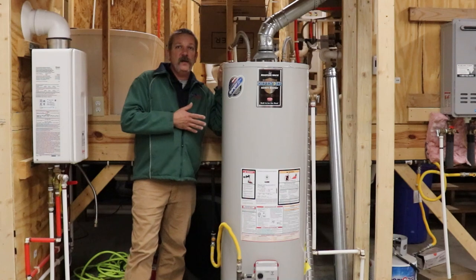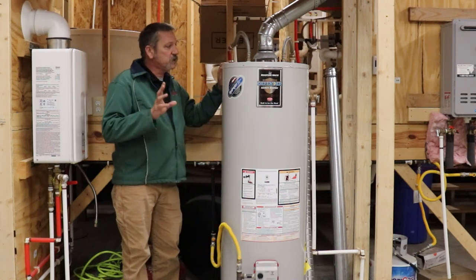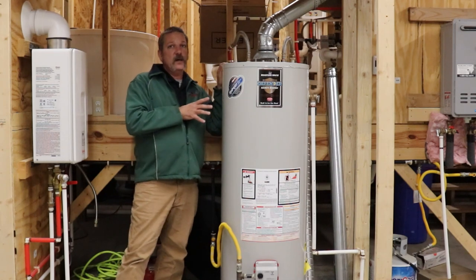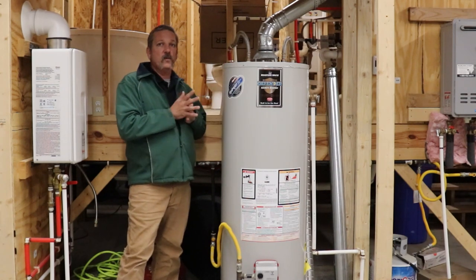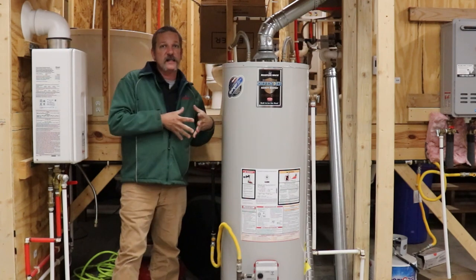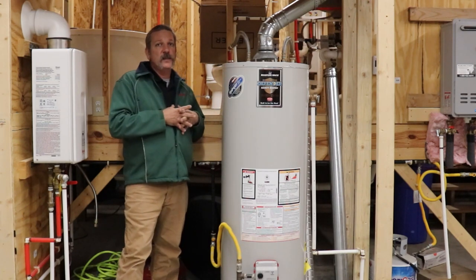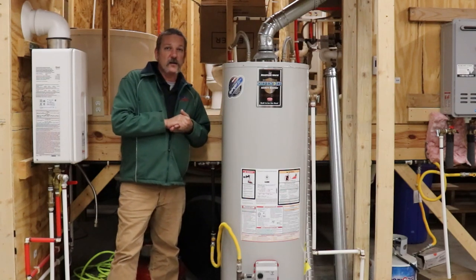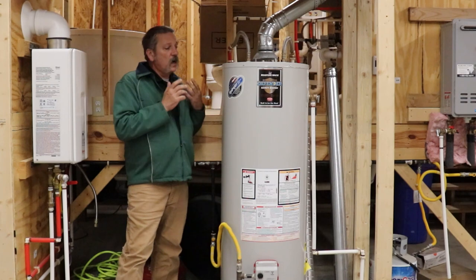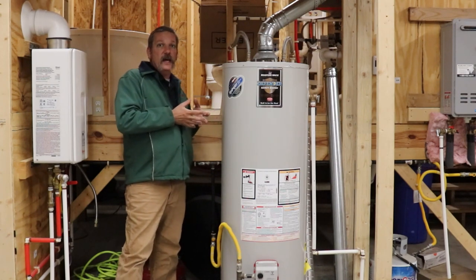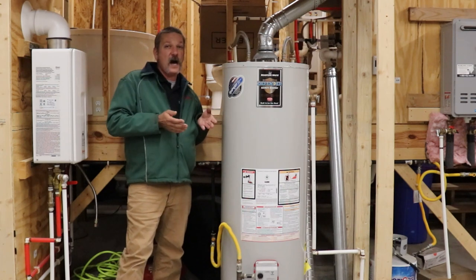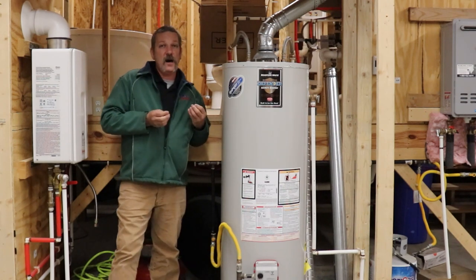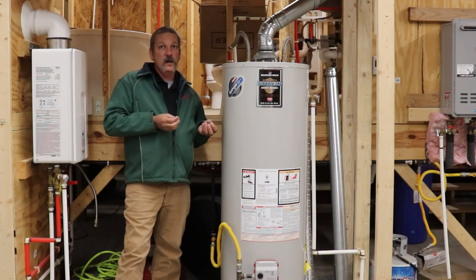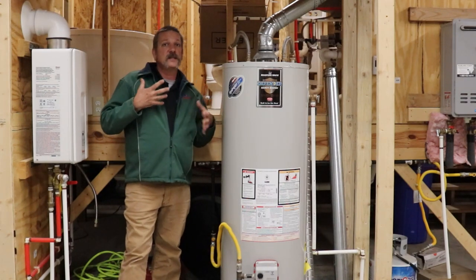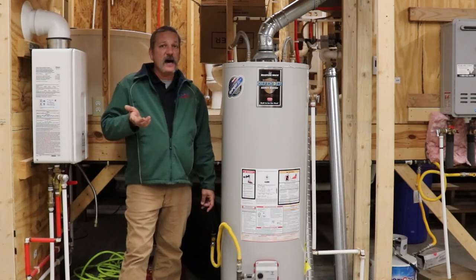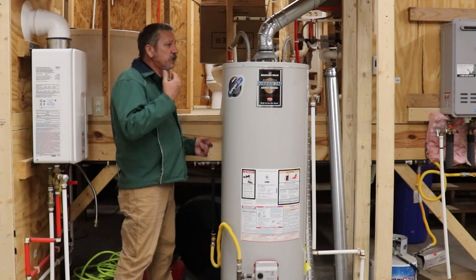Now, those UEF codes, those percentages, are displayed in a decimal. You're not going to see a whole lot of that in the advertising when you're looking around for these water heaters, because they're going to tell you, oh, it's glass lined, it's got this feature and this feature. It's because those energy factor codes are really, really low. A heater like this, a gas tank heater, is going to get you somewhere between 0.55 and 0.70. That's not really a good energy efficiency code. Most of your tankless water heaters are going to run somewhere around 0.8 to like 0.95. So a lot more energy efficient than these guys.